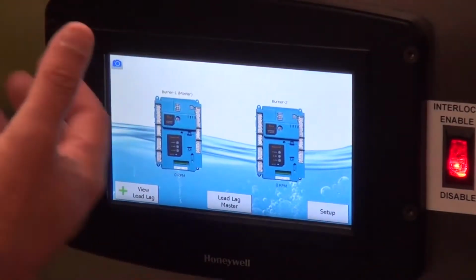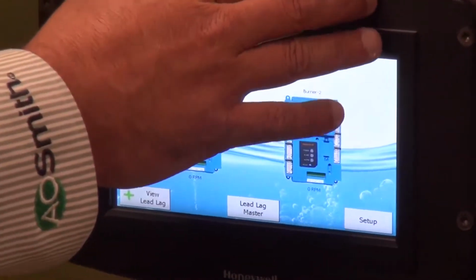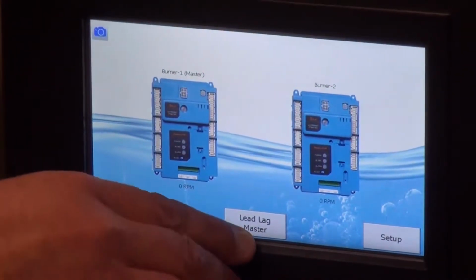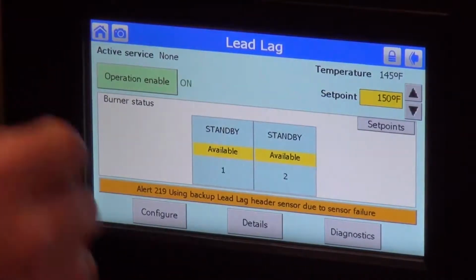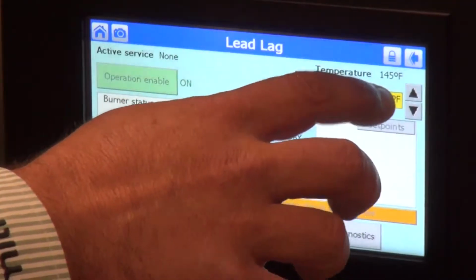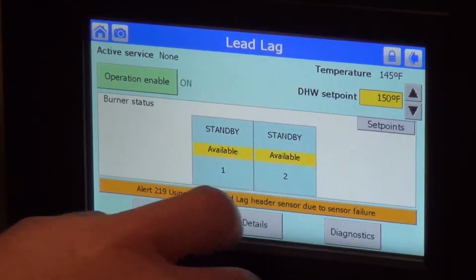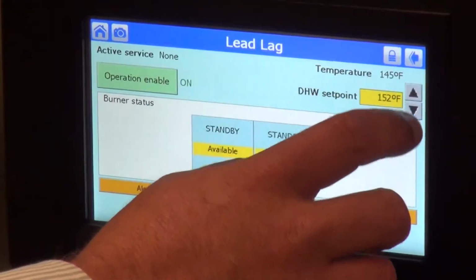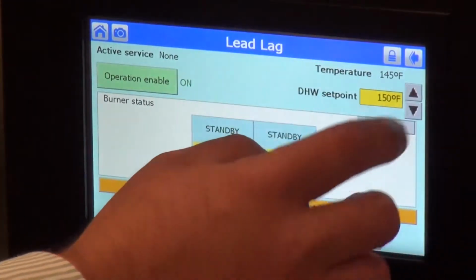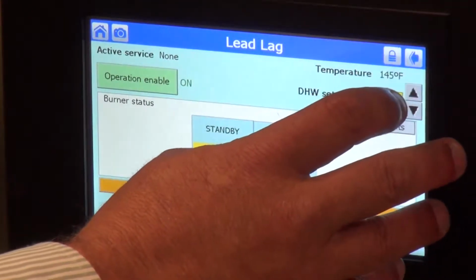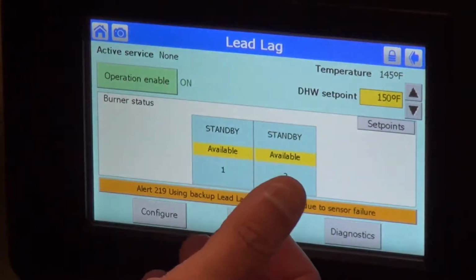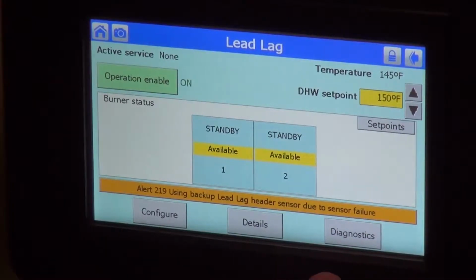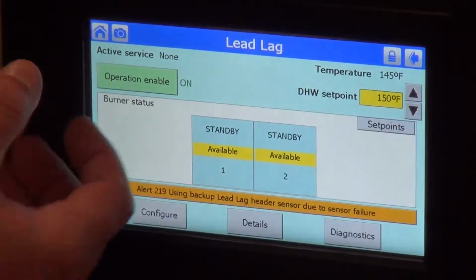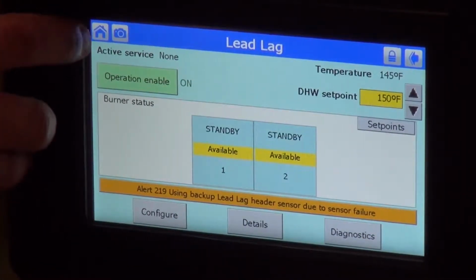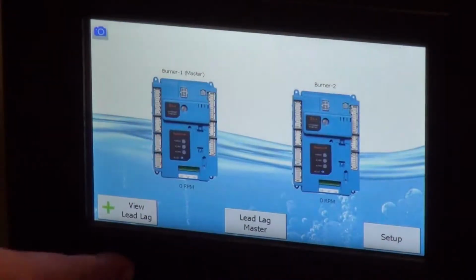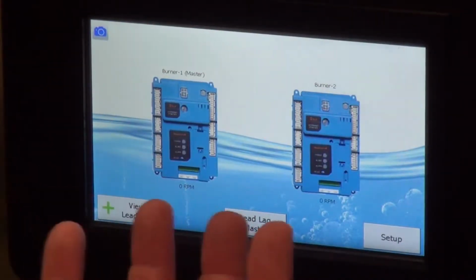But first things first, if we wanted to see what this boiler was set to, we're going to hit lead lag master. And then we're going to see the set point here. We're going to hit that little set point controller, we're going to hit OK, and then we can adjust what we want to do. I'm going to leave it at 150, but that's all you do to set it, and then you're set on the actual boiler itself for the temperature of the heater. If you want to go back to the original menu, we'll hit this little house. As we hit that house, it takes us all the way back to the controller, and that's really how you set this.